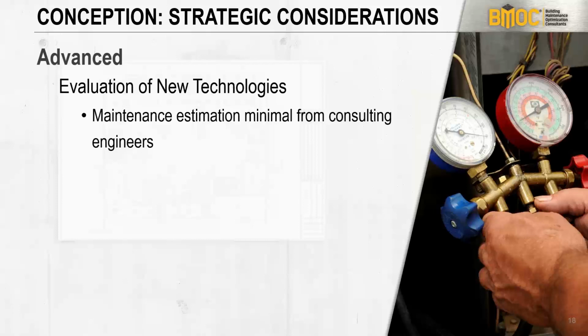So the assumption is that, in some cases of very experienced engineers, you might see this, but in general, they're just looking at the installation cost, the initial cost, versus payback in terms of energy savings. And they don't take into account any differential in maintenance. So they won't look at alternative A and alternative B and say, well, this is the difference in maintenance costs between the two, so we're going to deduct that from our energy savings calcs.